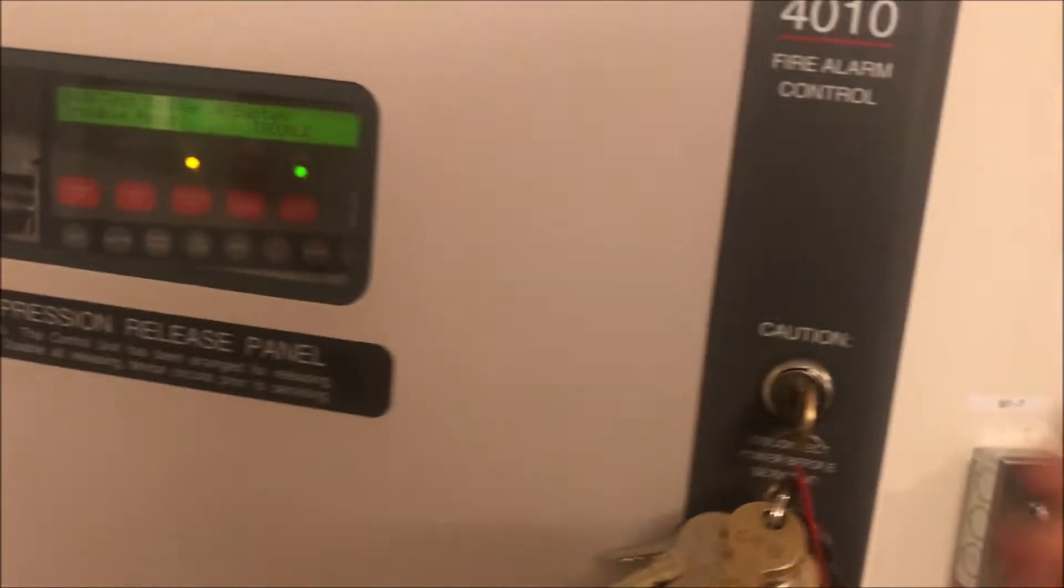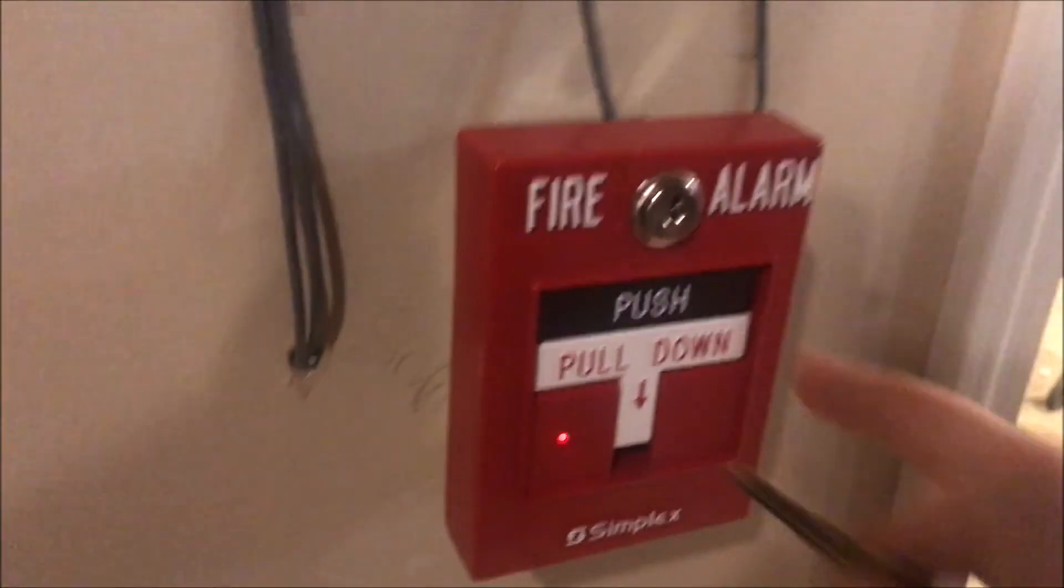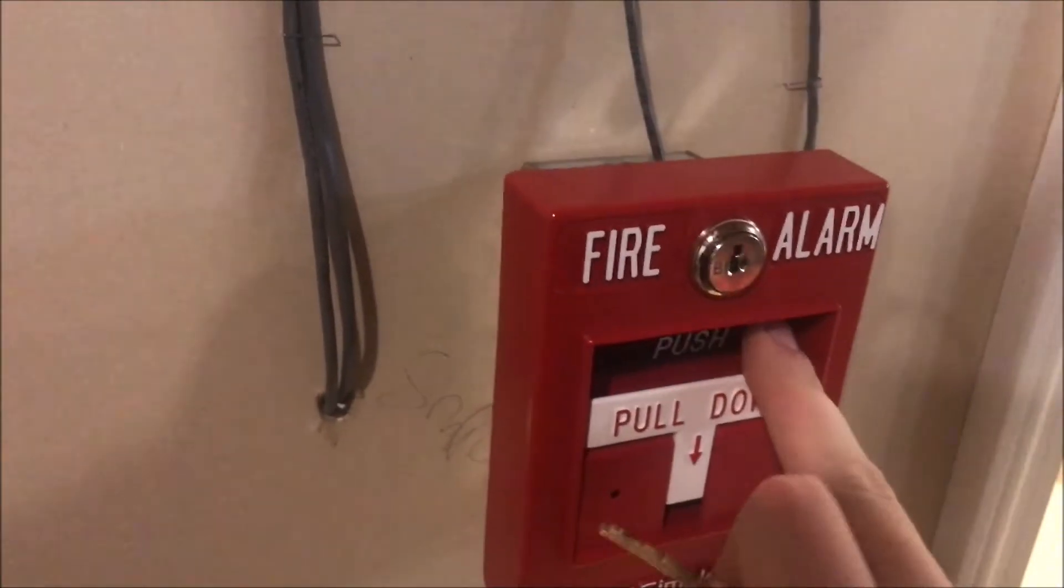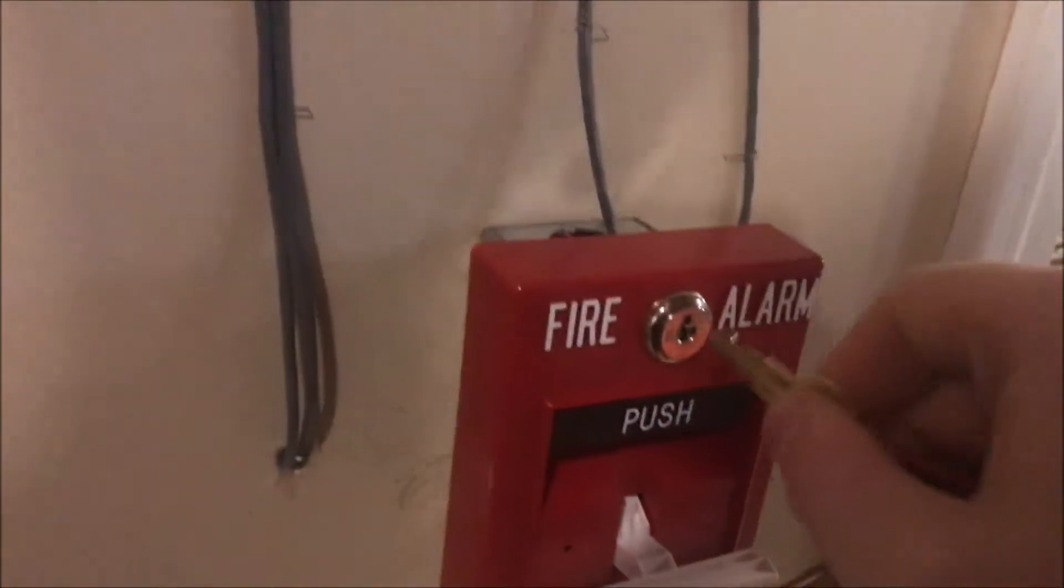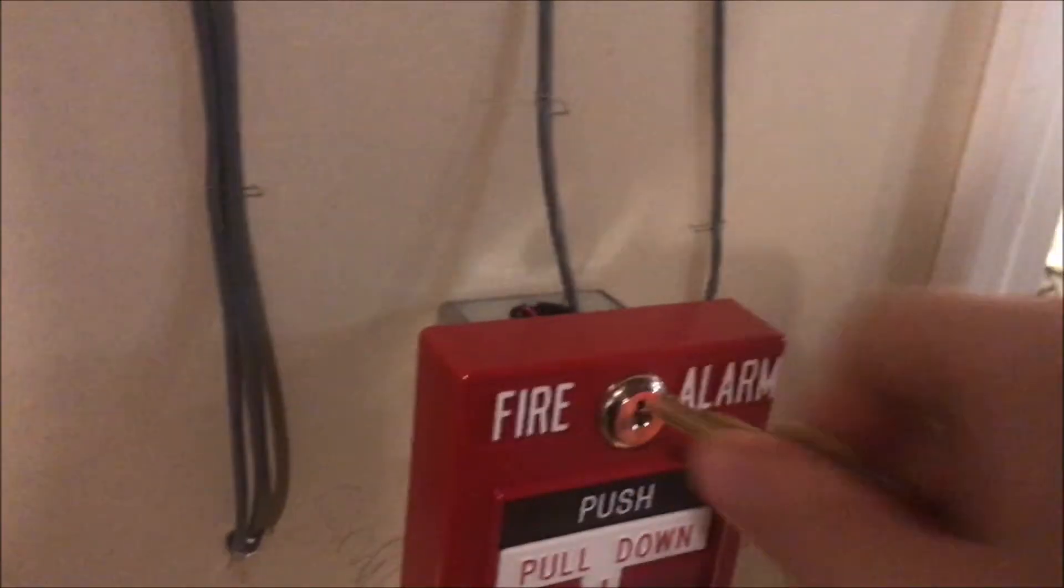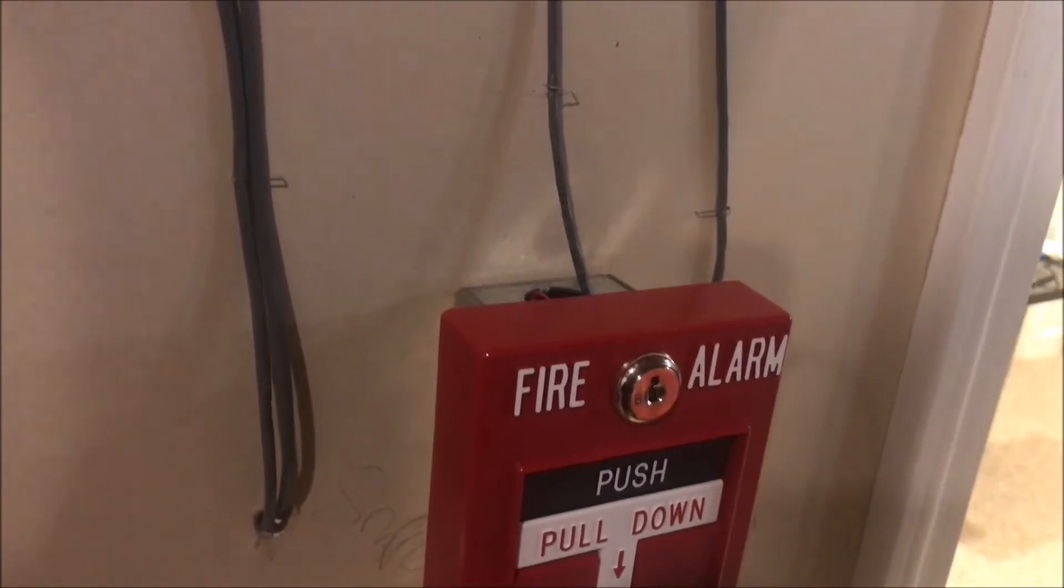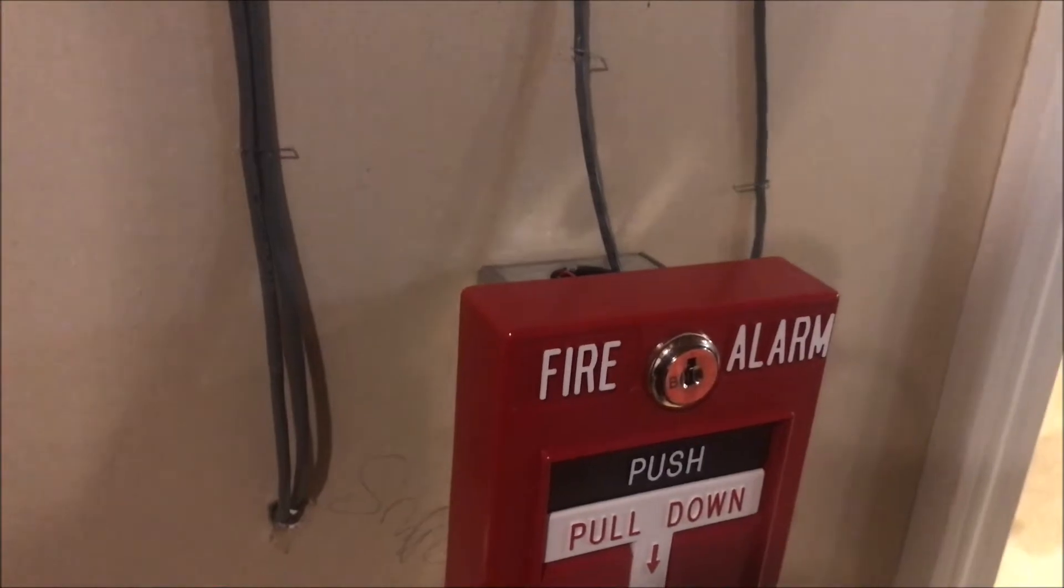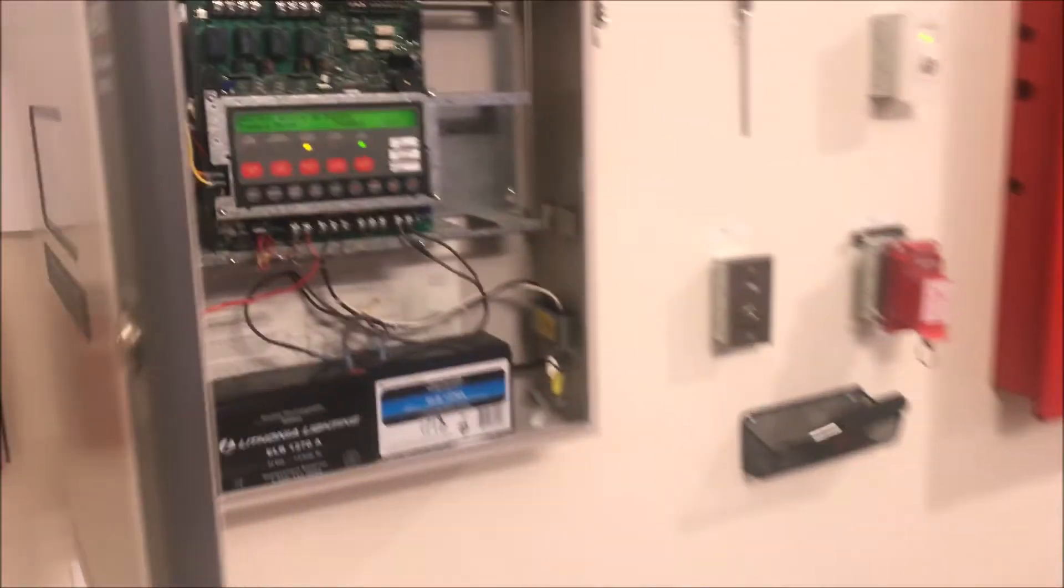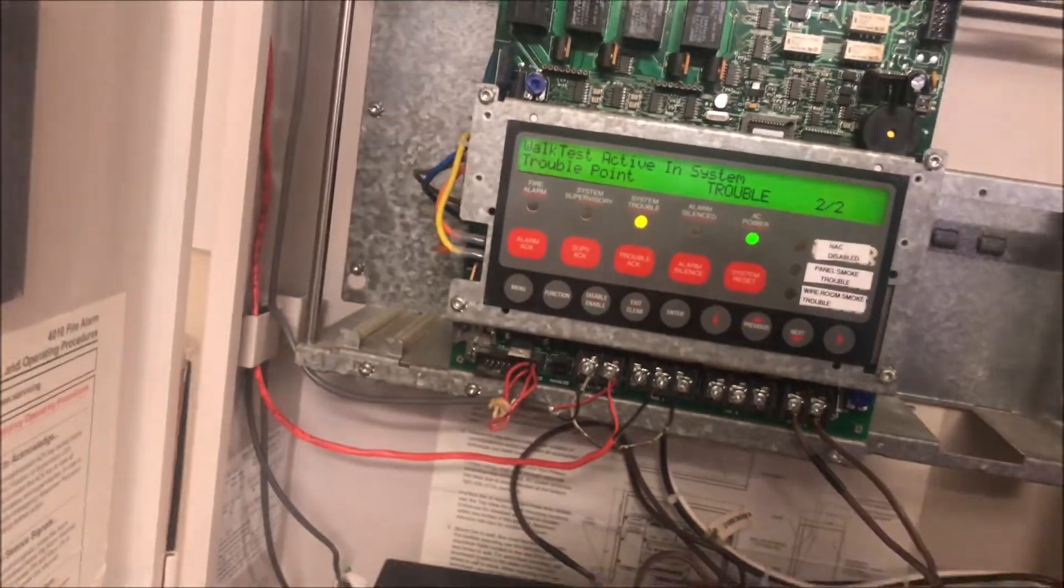So now if we go and pull that point, it should pulse the signals at 13. So let's do it. And there's our 13. So we now have successfully added a new IDnet point on a Simplex 4010.